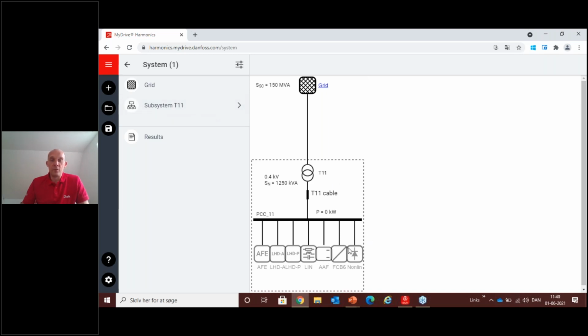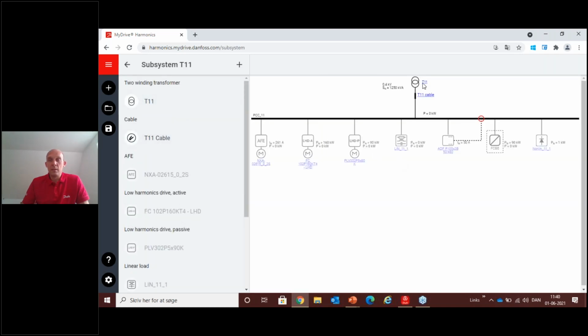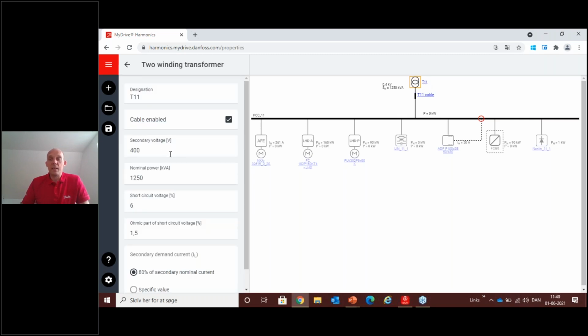What I'm interested in is of course knowing what goes on in my lower level, so I'll go down to the lower level and I'll start by giving the information about the transformer. Here you will be asked about the transformer data, and that data you can find on the nameplate on the transformer, or you can ask your power utility. They have to provide that to you. It asks which voltage you have, so 400 volts. It asks about the nominal power rating of your transformer, and I'll just take a 1600 kVA transformer, and it asks about the short circuit voltage percentage of the transformer, so I'll use 5% in this specific example. These three values are nameplate data, so it should be quite easy to get from the power utility, or if you have the transformer in your facility, you can look it up directly.